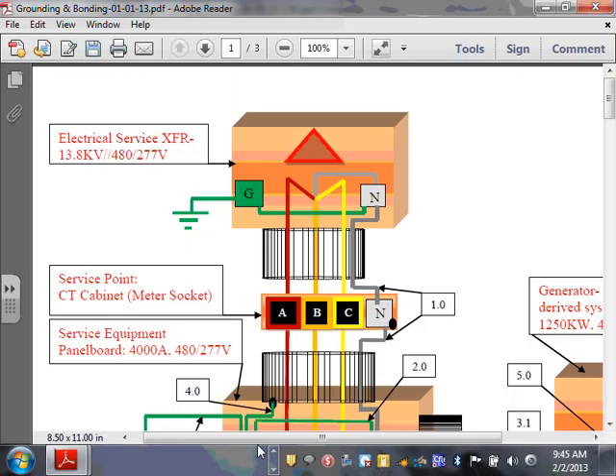So the common mistake, guys, when I teach electrical design and when I do training, is a lot of contractors and engineers want to pull an equipment grounding conductor from the service into the transformer. So this is the service entrance conduits coming in here. They want to pull an equipment grounding conductor. Not required. You can if you want to, but Excel does not allow you to. So between the transformer and the termination box or the CT cabinet, you're really pulling three conductors, typically pulled by Excel or whatever your agreement with them.